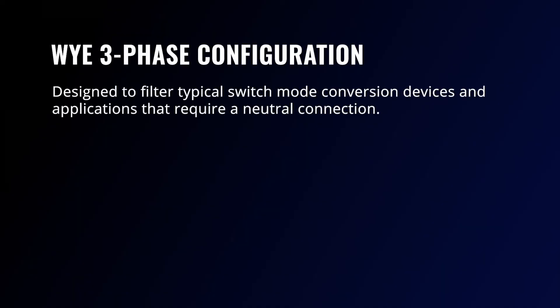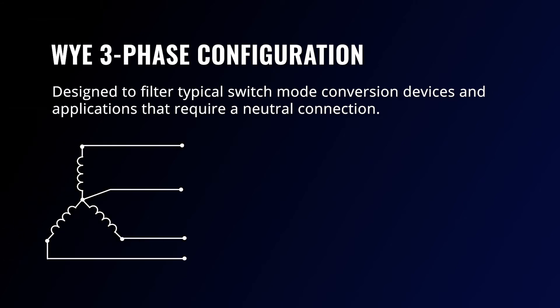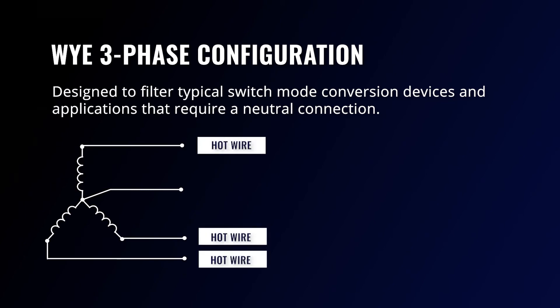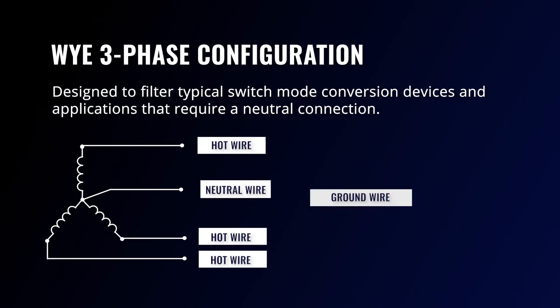Y EMI filters are designed to filter typical switch mode conversion devices and other applications that require a neutral connection. This configuration is composed of five wires: three hot conductors, a neutral wire, and a ground wire. In a Y configuration, the three-phase loads are connected at a single point. This configuration allows the use of lower voltage capacitors, which can lead to savings in cost, weight, and volume.